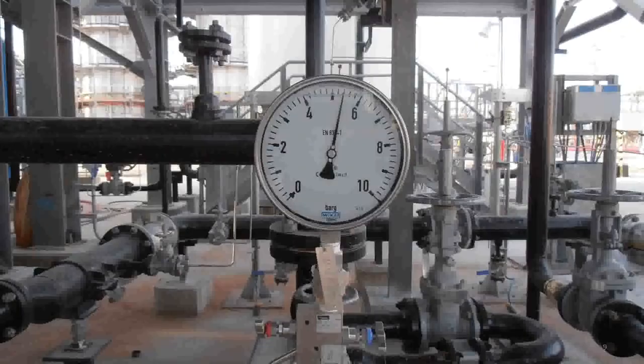Class of the instrument is absolute error of measurement expressed as percentage of instrument range. For example, if a pressure gauge has the range of 0 to 10 bar and the class of 1, its absolute error of measurement is 1% of 10 bar equals 0,1 bar. Absolute error is the same on the whole range. Relative and percentage errors are smallest at the end of range, and the greatest at the beginning of range.